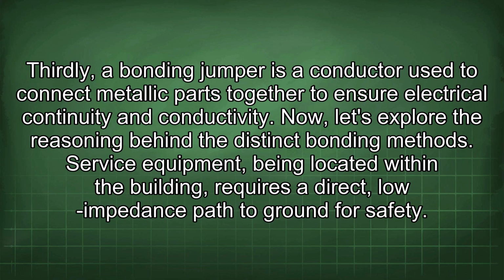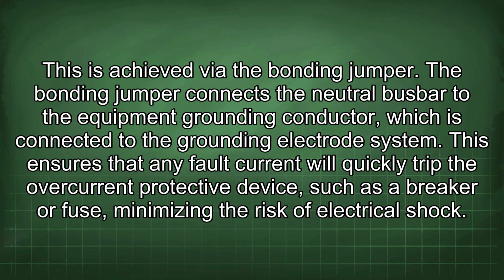Service equipment, being located within the building, requires a direct, low impedance path to ground for safety. This is achieved via the bonding jumper. The bonding jumper connects the neutral busbar to the equipment grounding conductor, which is connected to the grounding electrode system. This ensures that any fault current will quickly trip the overcurrent protective device, such as a breaker or fuse, minimizing the risk of electrical shock.